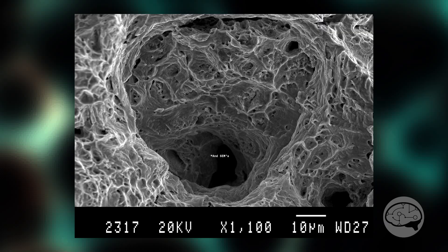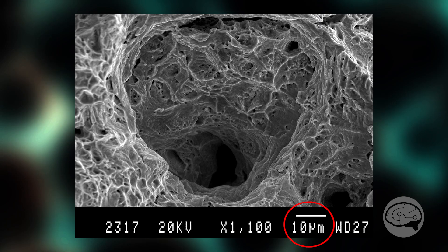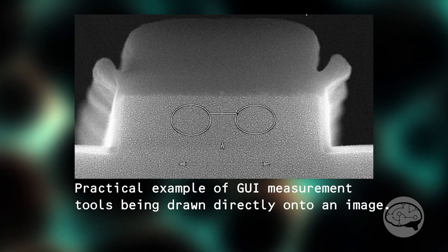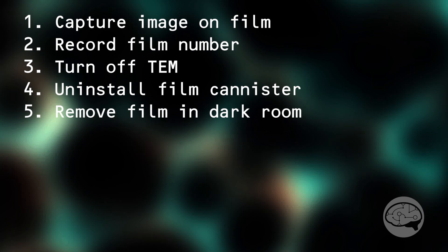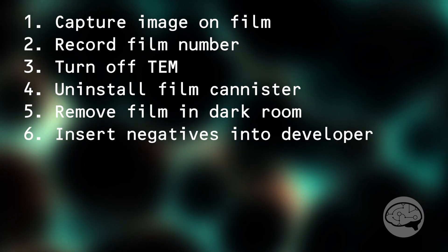On modern digital TEMs you'll have a magnification marker on the screen as well as measurement tools you can draw on your computer screen. However, in these pre-digital days, in order to get a measurement of something, this is what you'd have to do: take an image on film, write down the film number so you know which image was yours, turn off the TEM, take the film canister out of the bottom of the TEM, and in a pitch-black dark room remove the exact number of pieces of film that you exposed and put them in the developer. Then you'll have your little TEM negative.